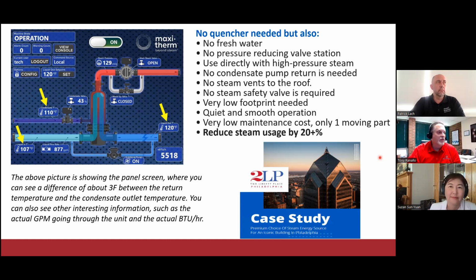The other thing about this being a vertical pattern design is it has a very small footprint, and you can get a lot of horsepower, a lot of pounds per hour throughput in a very small form factor. The unit is quiet with smooth operation. You will not hear a sound from this. There is no water hammer. There's no sizzling from steam coming through steam traps or anything like that. Very quiet. And because there's only one moving part, which is our condensate control valve, very low maintenance. As you saw in our previous slides, we can reduce steam usage by up to about 20%.